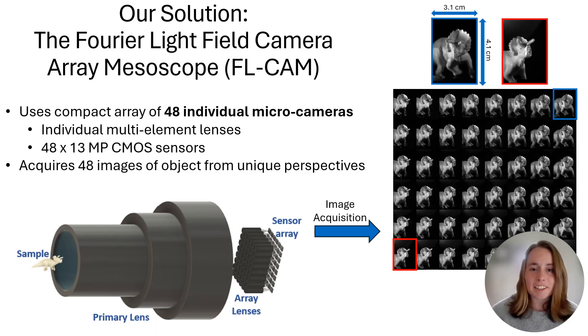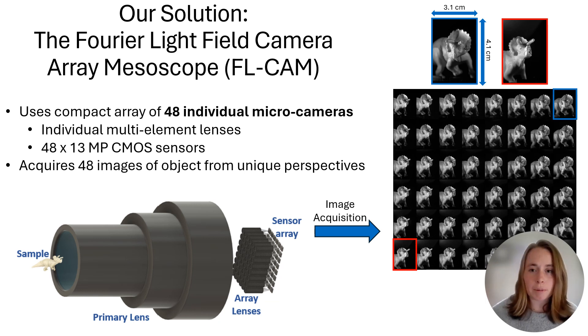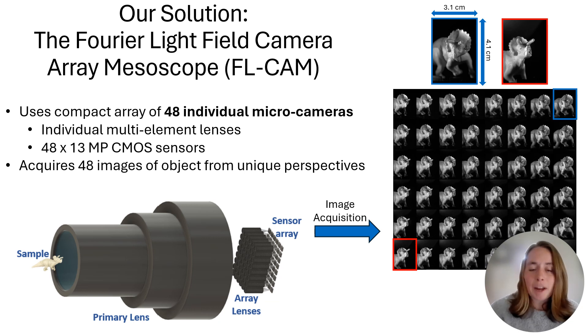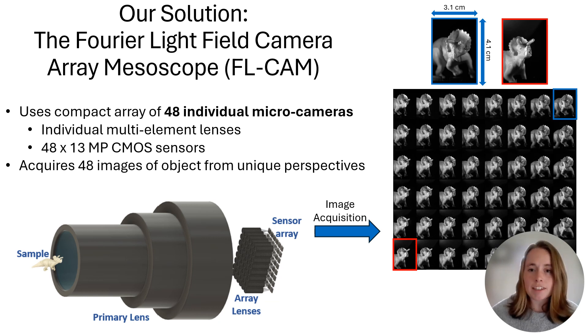Our solution to this challenge is the Fourier light field camera array mesoscope. In designing this system, we took concepts from Fourier light field microscopy, which is an established 3D microscopy technique, and applied them over a larger scale. The Fourier light field camera array mesoscope, which I'll be referring to as the FL cam, uses a compact array of 48 synchronized micro cameras, each of which has its own multi-element lens and high pixel count CMOS sensor.